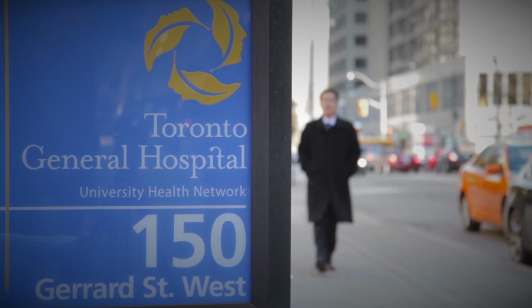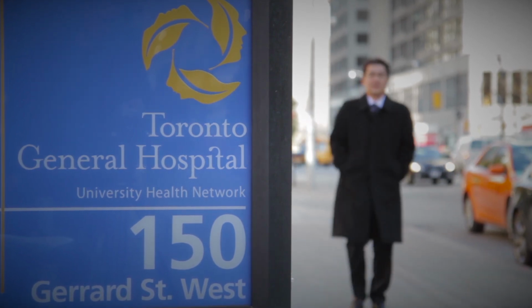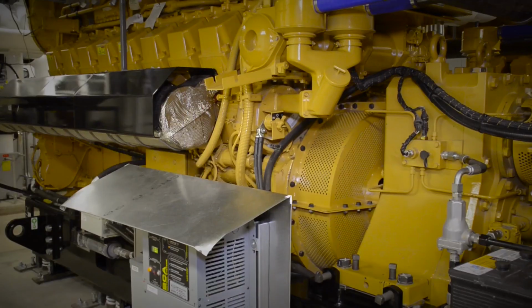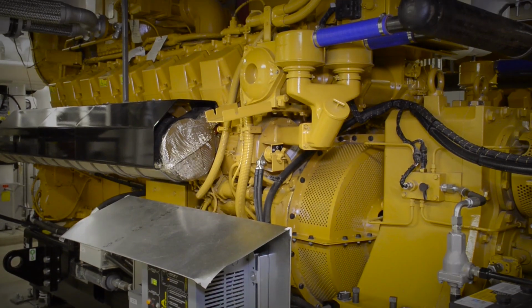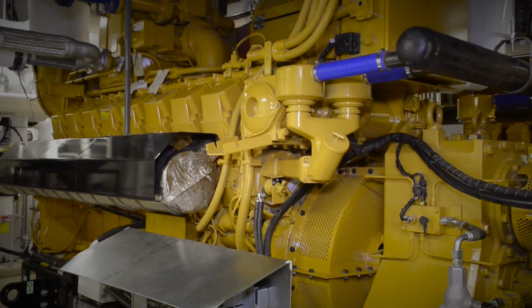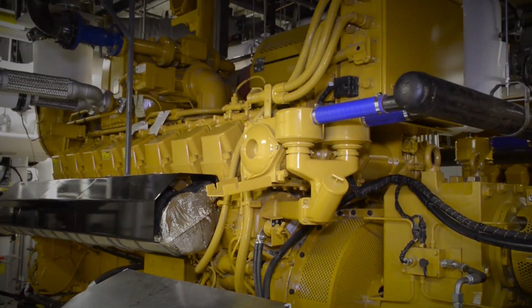The primary business of the facility is to provide a stable steam service to our critical hospital customers. The electricity from these generators gets directly exported out to the Toronto Hydro grid in downtown Toronto. Whatever we use in-house, we use first, and then the balance goes out to the grid. We run basically as the province's virtual power plant, and we'd expect to run somewhere between 1,000 to 2,000 hours a year.